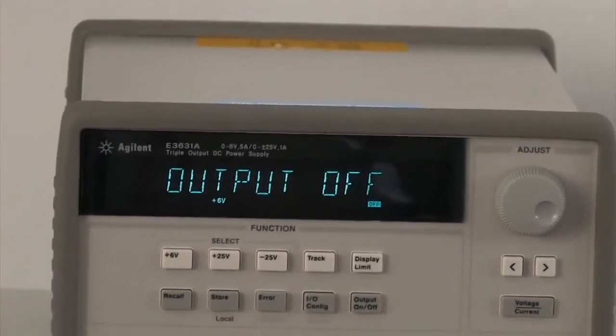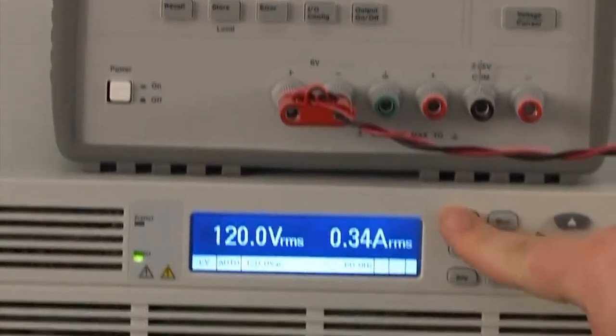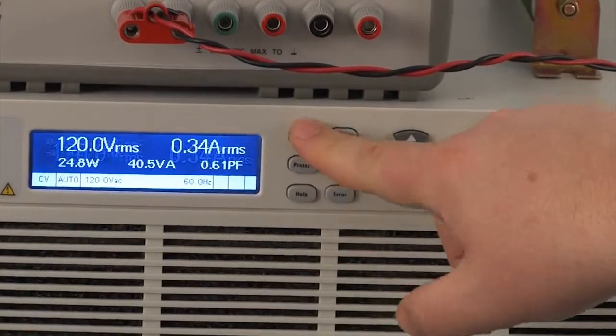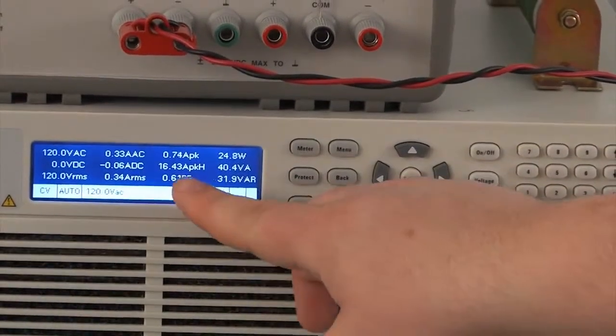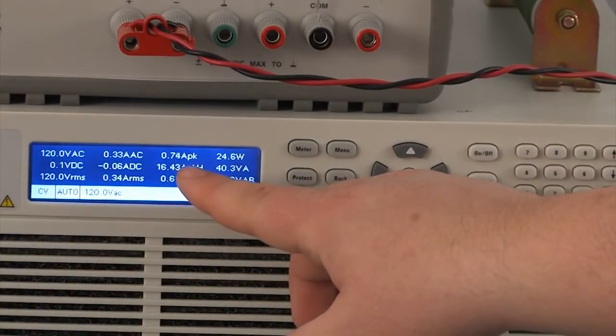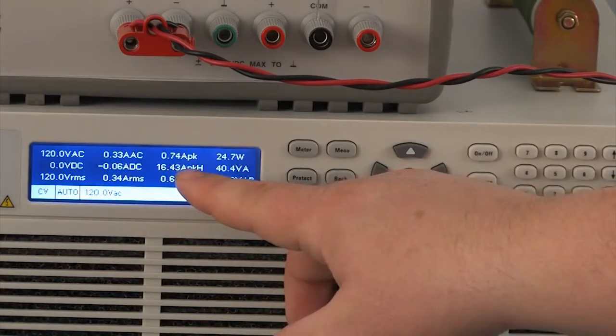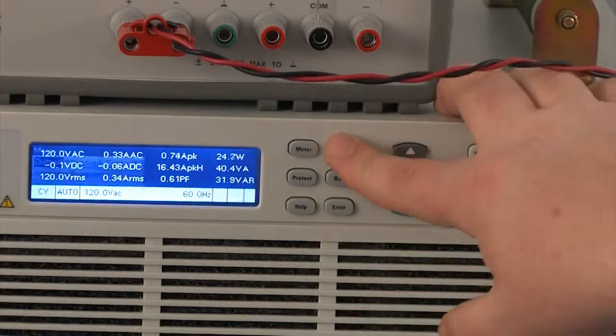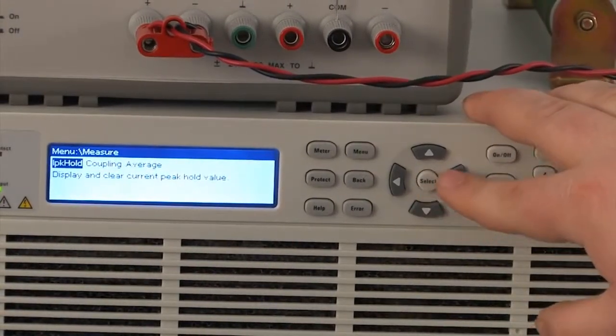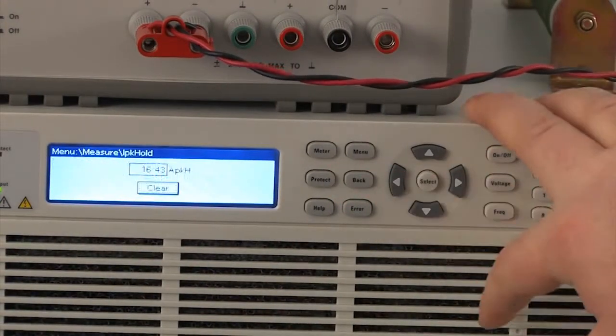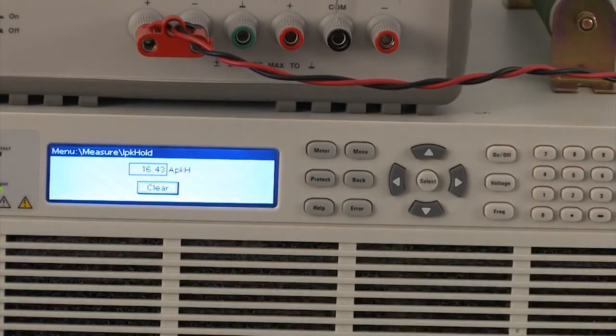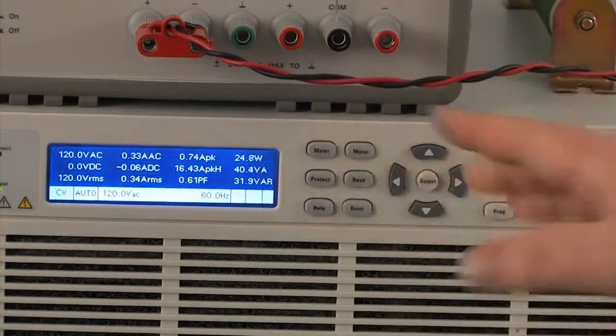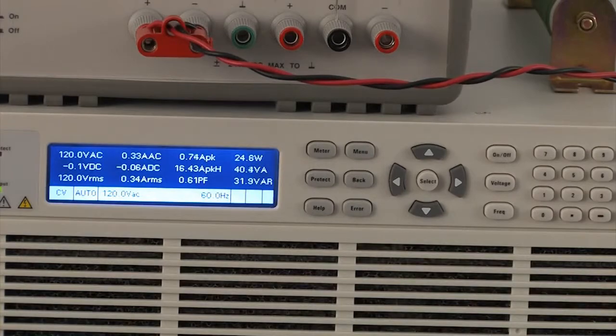So now what we're going to do to get the actual in-rush measurement is we're going to hit meter. If you hit meter twice you could actually go and get the IPk-Hold right here. So you can see we measure 16.43 amps. You could also go to the measurement menu here and click on this IPk-Hold and you get the same measurement here. So that's kind of how you would do an in-rush current test from the front panel.